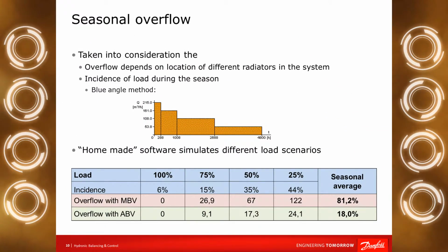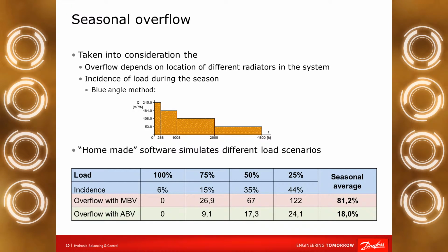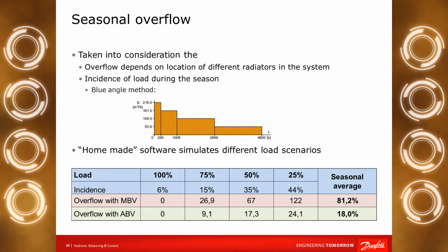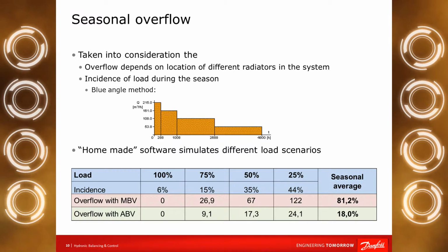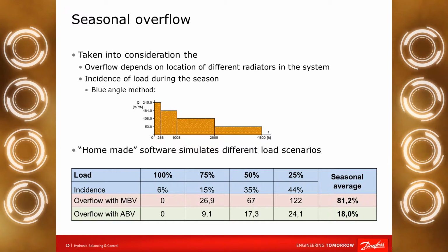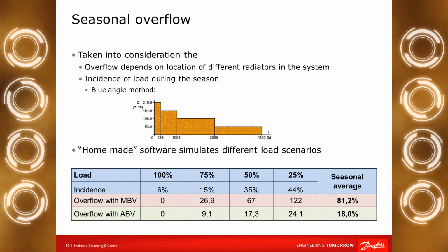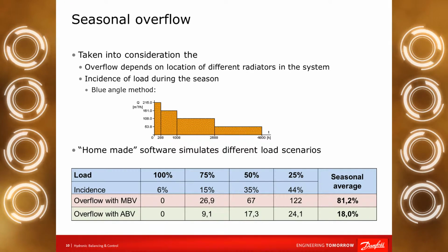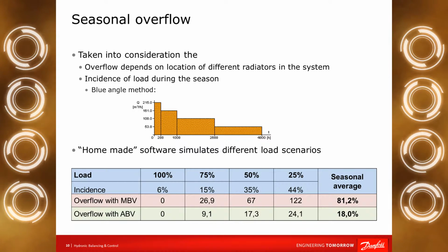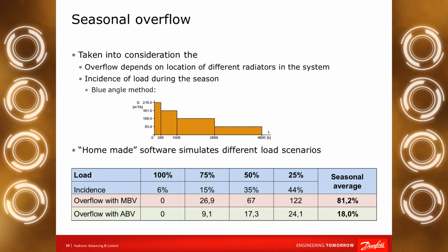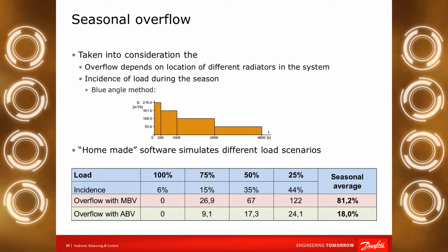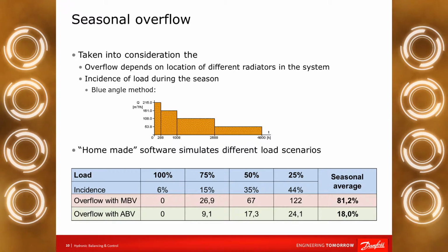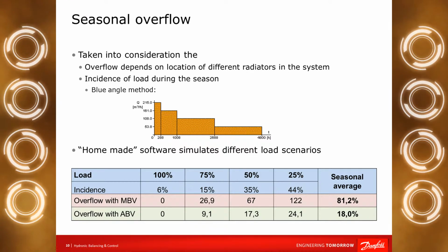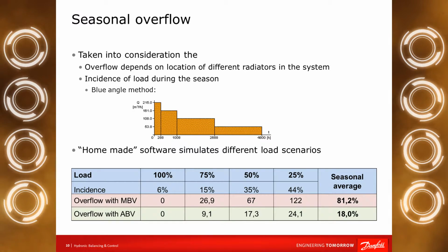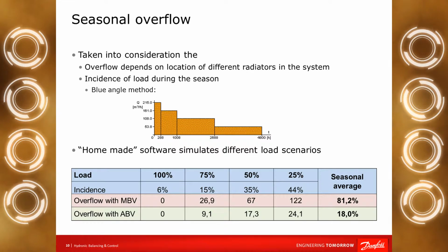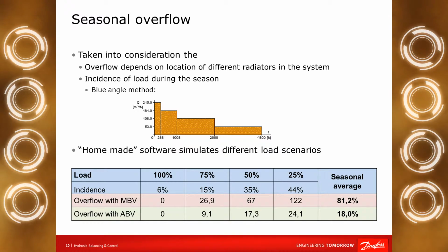But to know more about the system, we have to check what is the seasonal overflow in the total system. Because the overflow depends on the location of the thermostatic radiator valve, the terminal unit in the system. It depends on the incidence factor, how many hours we are working in different load profiles, 75, 50, 25, or 100% load. For this calculation, I use the Blue Angel method, which is most often used by pump producer companies to show what is the seasonal average incidence factor. You can see here, for example, for the 25% load profile, we have the longest time in the whole season. And we have to take this into consideration in our calculation.